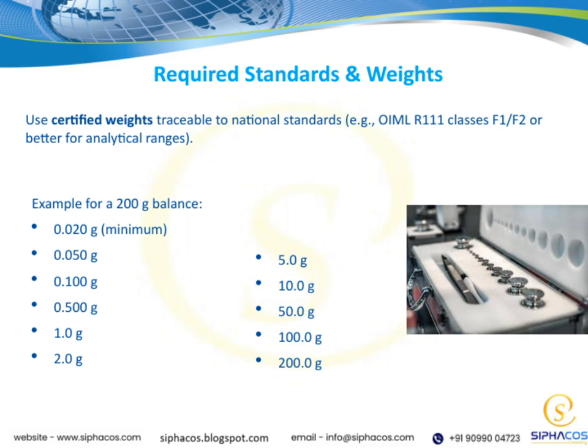Now, looking at the specific weights, you'll see common values like 5 grams, 10 grams, 50 grams, 100 grams, and 200 grams. These are typical standards used for calibration, but the key is to select weights that match or exceed the required accuracy for your balance's range. Focusing on a 200-gram balance, for instance, the required standards include very precise weights such as a minimum of 0.02 grams, then 0.05 grams, 0.1 grams, 0.5 grams, 1 gram, and 2 grams.